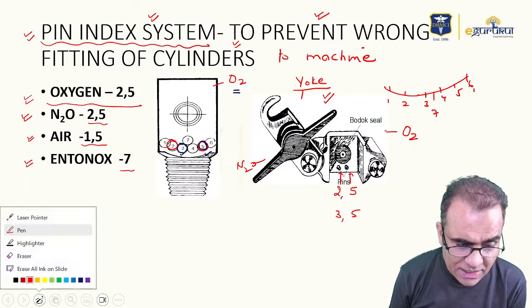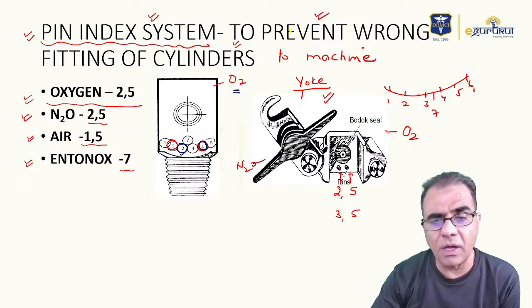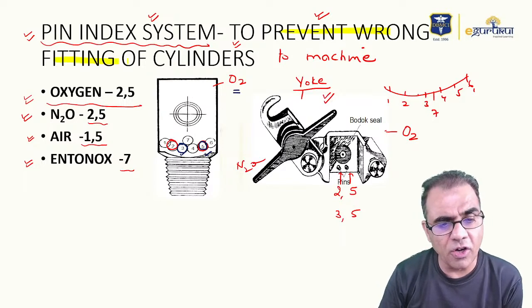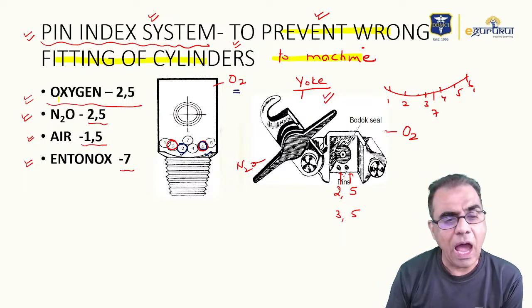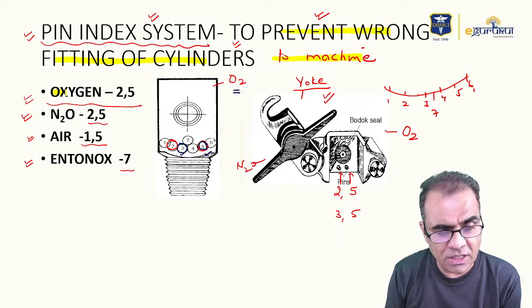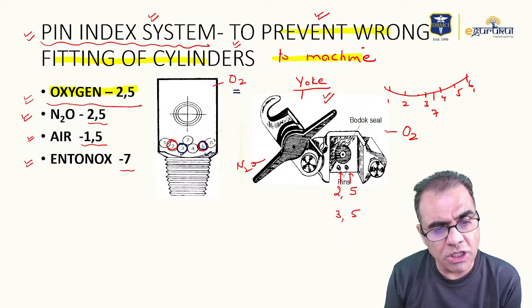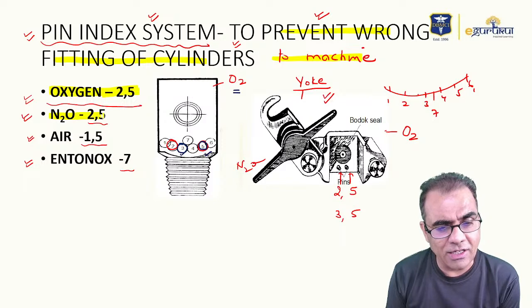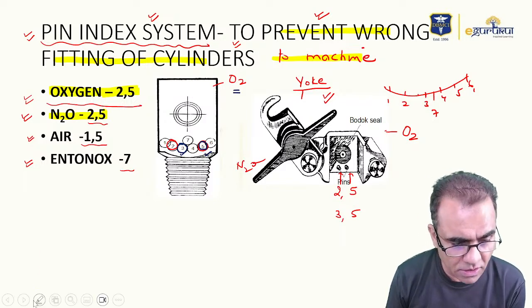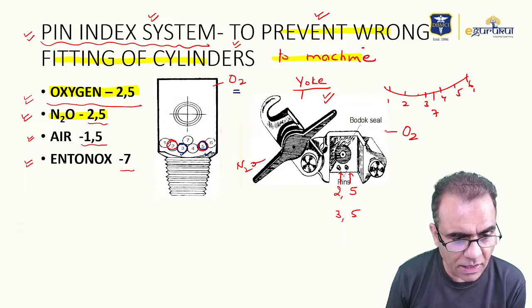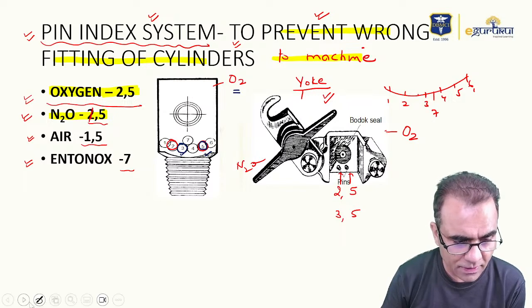So the pin index system is a very important protective mechanism to prevent wrong fitting of cylinders to the anesthesia machine. Pin index positions: oxygen, 2 and 5. Nitrous oxide, sorry, it is 3 and 5, I think. It's a printing error, so you can correct it.